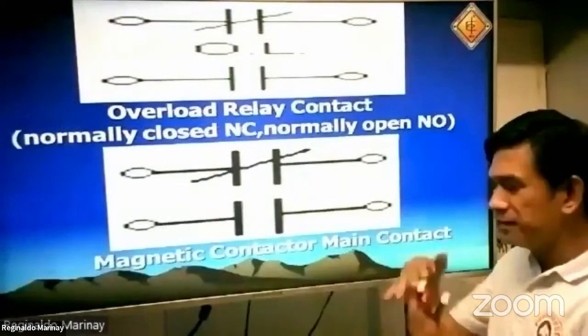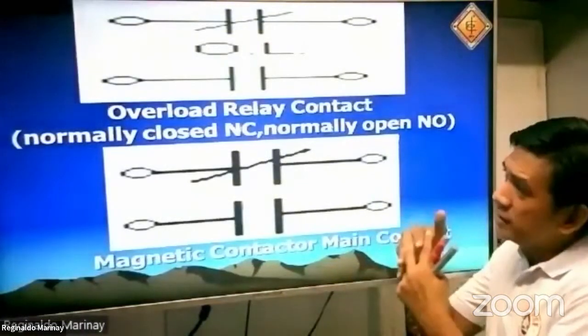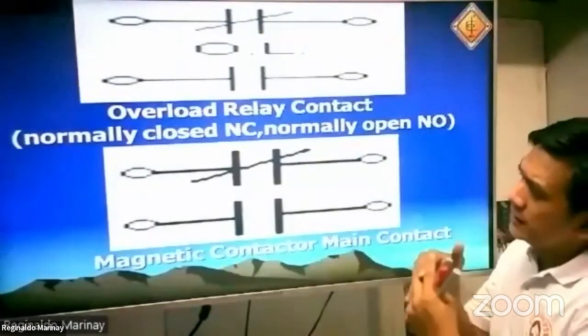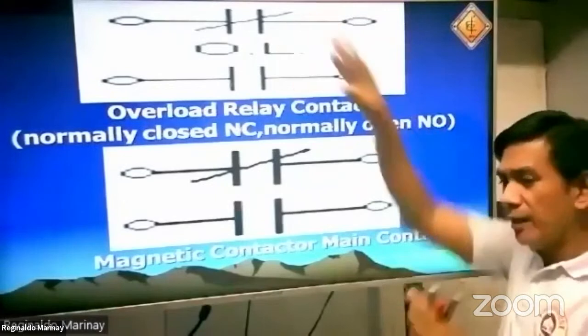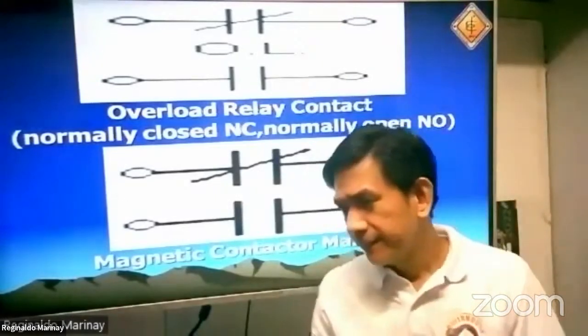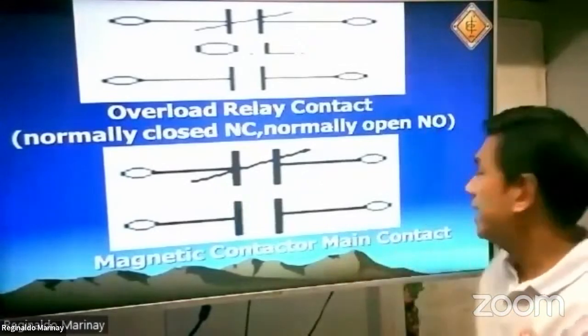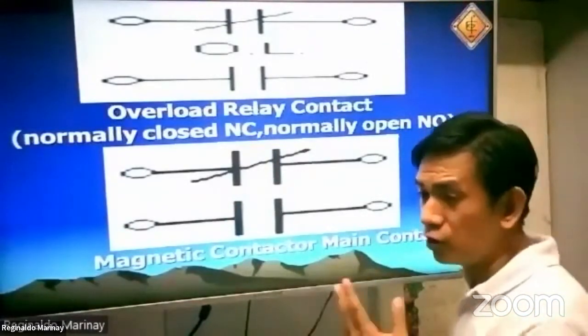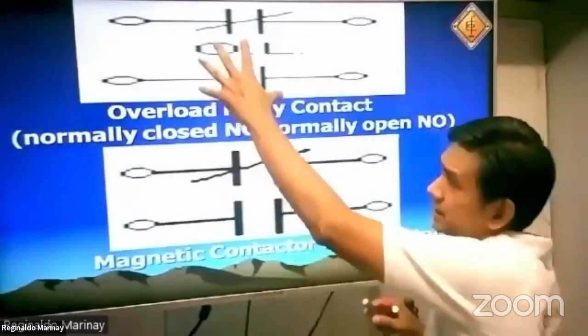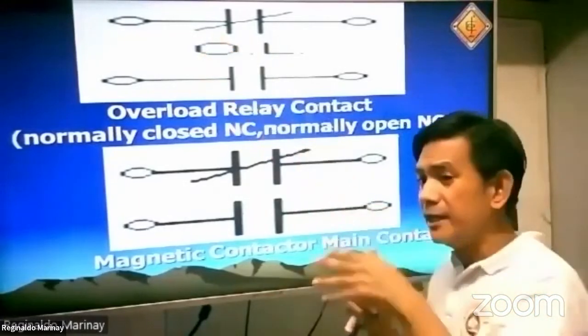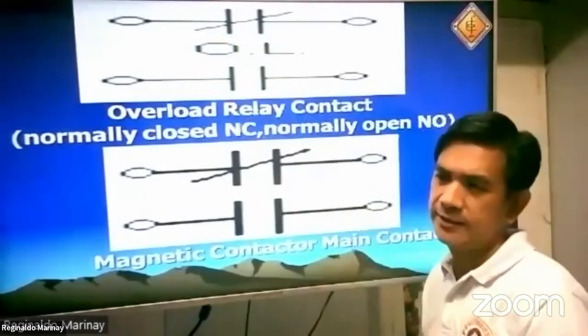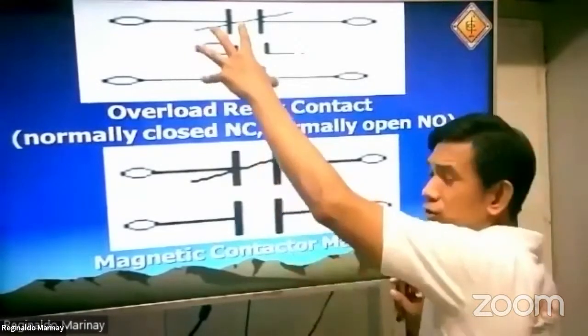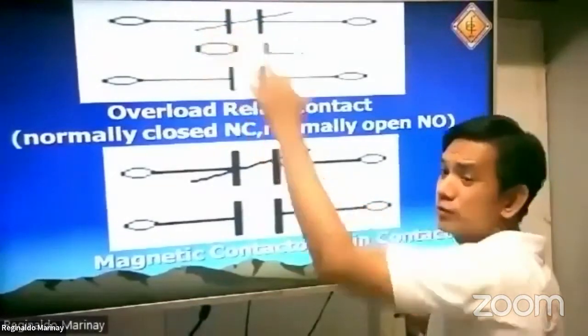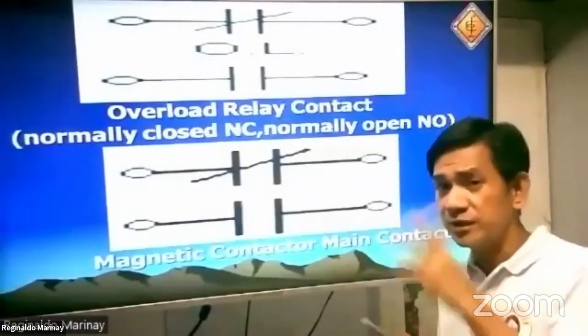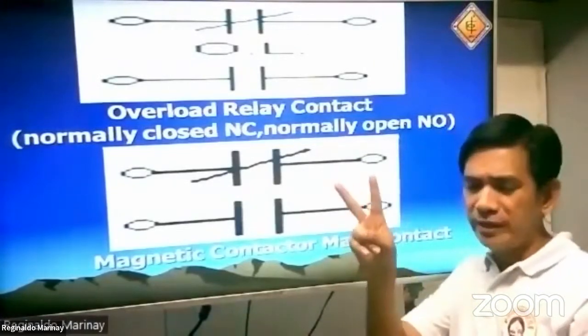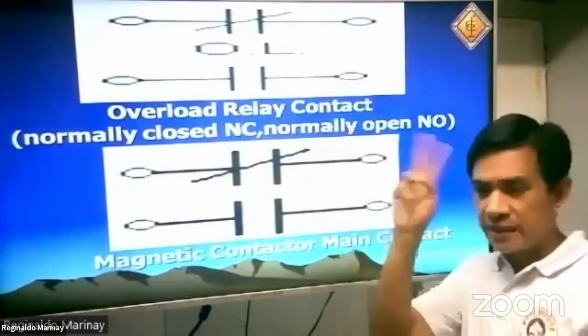So, usually the magnetic contactor is attached with the overload relay. You will see here that the overload relay also has a contact. An overload relay has a heater element and a contact. What is the function of this contact? The heater element is connected to the motor circuit, to the motor or power circuit. The overload contact is basically connected to the control circuit. Always remember that the motor control circuit has two parts or two components, the motor circuit and the control circuit. Remember that.